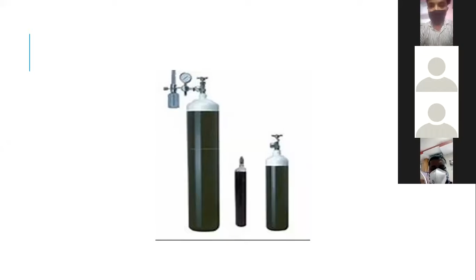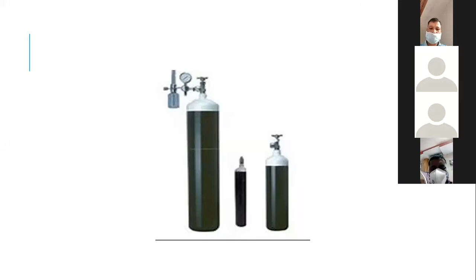One thing you have to know is that with this 2,200 psi, nobody will give oxygen to the patient. That much pressure, if it goes, will cause what you call barotrauma, or lung trauma. So that is the reason why we have to reduce the pressure and deliver oxygen at a level of 10 to 15 psi. You see, where is 2,200 psi and where is 15 psi?